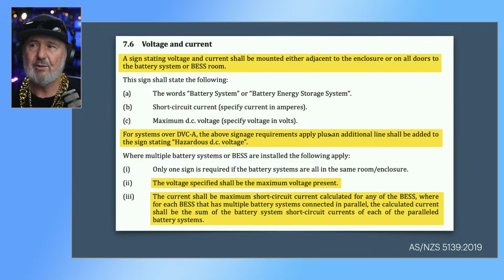Please note on that second highlighted clause, for systems over 60 volts DC, that's above DVCA, you require the hazardous DC voltage sign as well. That's just to indicate there's a higher risk. And where there are multiple battery systems or BESSes installed, the following apply. Only one sign is required if all the systems are in the same room. Now, you've got to often think about the intent of a standard, certainly when it's not very prescriptive. This is first responder information. They'll do with it what they were trained to do. So if it says something that they've been made aware of, that they shouldn't spray water on it because it's potentially a dangerous conductive voltage, they will respond to that.